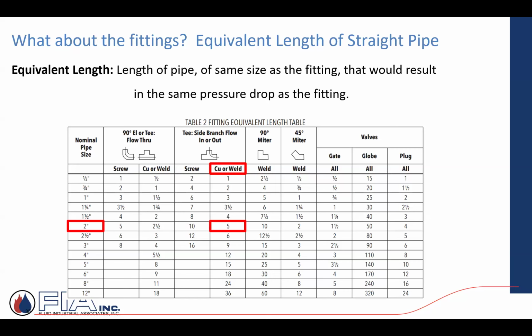So as you're designing this pressure drop and you're designing the system, well, yeah, there's going to be a tremendous amount of straight run of pipe. But there's also going to be fittings, T's, elbows, etc. That needs to be accounted for. And at the end, you'll establish this TEL, total equivalent length. And that's what you're going to say, okay, my copper pipe, 30 gallons a minute, 2 feet per 100. What's my TEL to establish my total required pump head?